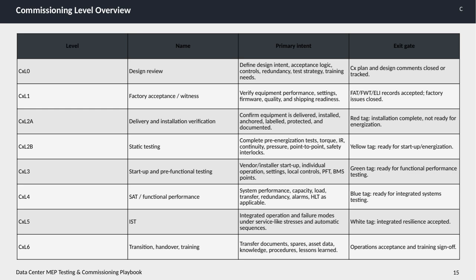At CxL4, system acceptance testing evaluates overall system performance, including capacity, load handling, transfer capabilities, redundancy, alarms, and heat load tests. Passing this phase gives a blue tag, authorizing integrated systems testing. CxL5, integrated systems testing, examines integrated operation and failure modes under realistic stresses and automatic sequences. This ensures the system's resilience and readiness, resulting in a white tag to confirm acceptance. Finally, CxL6 covers transition, handover and training. This level is about transferring documentation, spare parts, asset data, knowledge, procedures, and lessons learned to operations, with formal acceptance and training sign-off to complete the commissioning process. Each level builds on the previous, creating a thorough, structured approach to ensure the data center systems are reliable, safe, and fully functional before going live.